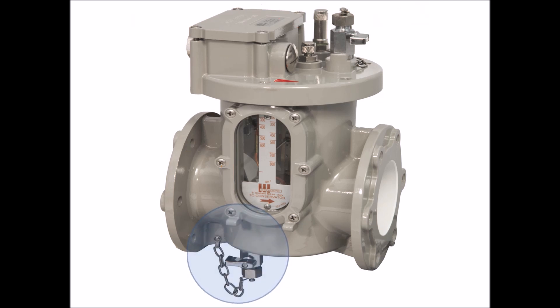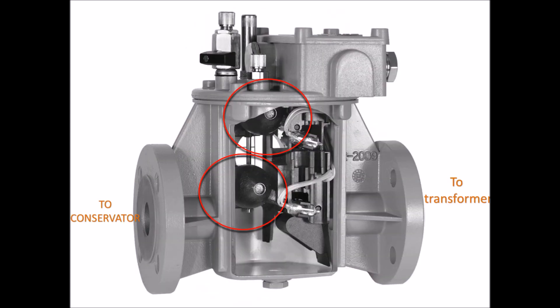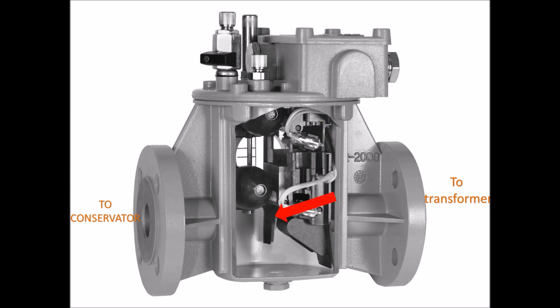A draincock is provided at the bottom of the casing for draining the oil. Two floats and magnetic reed switches are fixed inside the Buchholz relay at two different levels. The higher reed switch is used to produce an alarm, and the lower reed switch is used to trip the circuit breaker at the incoming side of the transformer. A flap is provided at the oil inlet to sense oil surge.